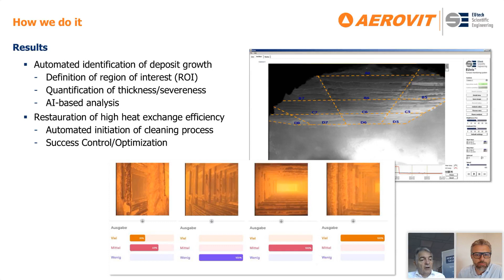But how can you do the cleaning? Well, this is where we have a solution that can help you. The Aerovit SC Jet solution is a shower cleaning solution that is fully automated for cleaning the empty passes after the furnace. You could do it according to temperatures, or you can do it according to a schedule. So you can have everything programmed up front, but sometimes you will have different mix of fuel. You will have different temperatures, and therefore it might be better to adapt the cleaning sequence according to the diagnostics that we've heard Michael talk about earlier. So you either visually see them or have the diagnostics to know exactly where to clean the boiler.